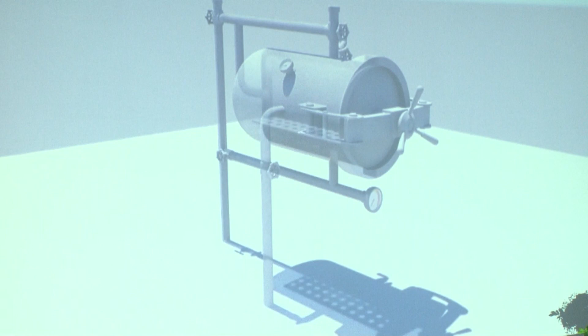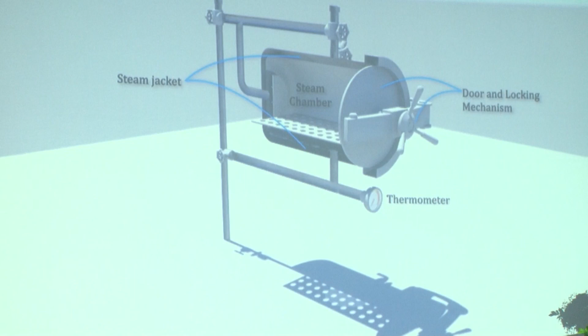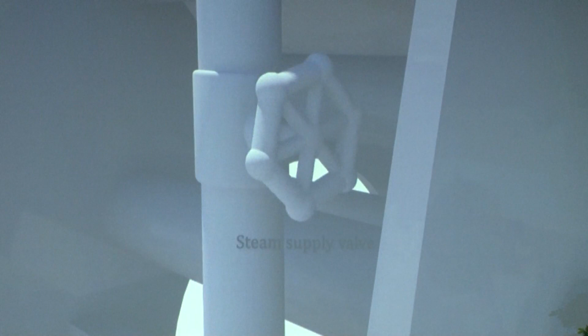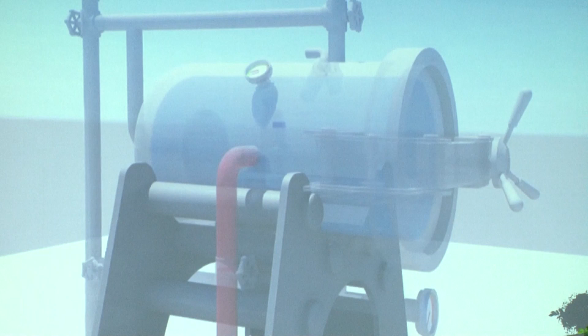So the autoclave, basically whatever autoclave it is, has 2 jackets, an inner jacket and an outer jacket, with a series of valves. These valves let in the steam inside the autoclave in a graded manner for the temperature to rise and sterilize your instruments. Most of the time, these valves are the ones which cause the leak, which causes a failure of the sterilization cycle. So you really need to know these valves, how they function, and change the gasket or whatever is possible to ensure that they work well. So this is a simple working model of how the autoclave works.